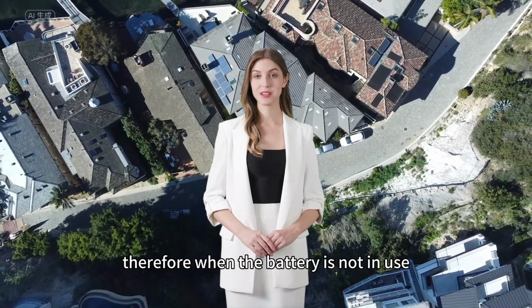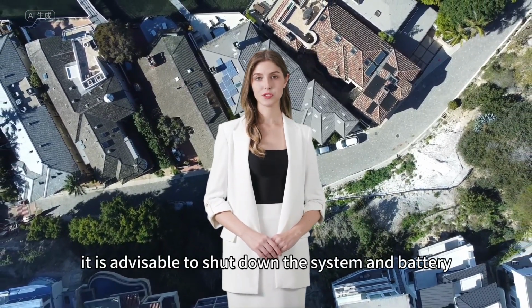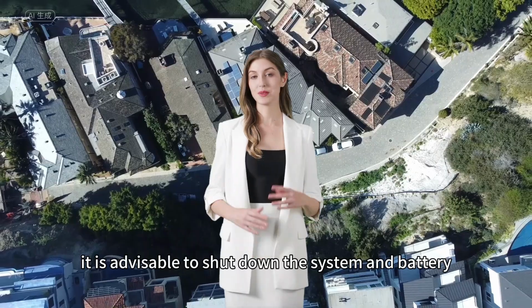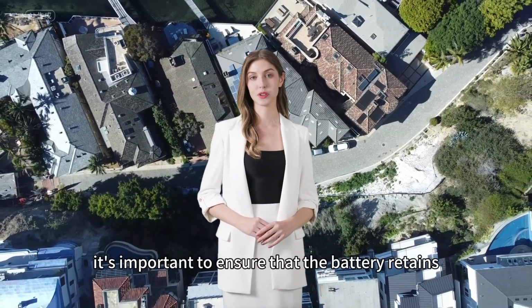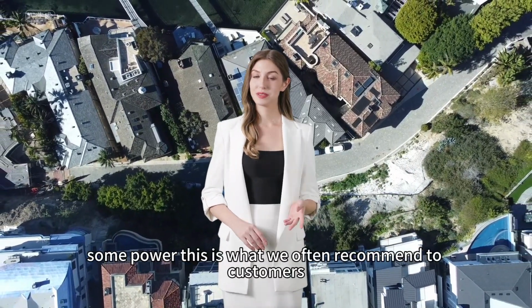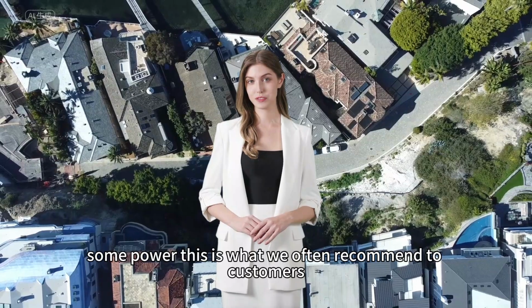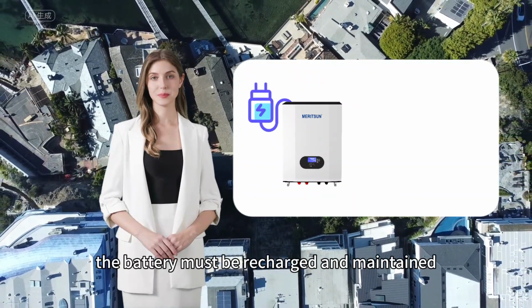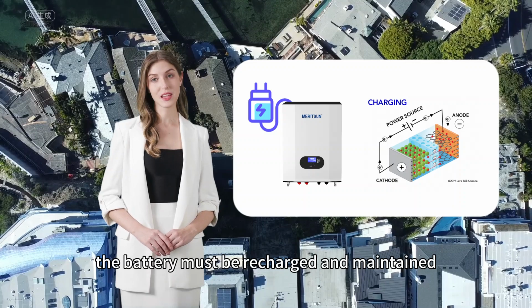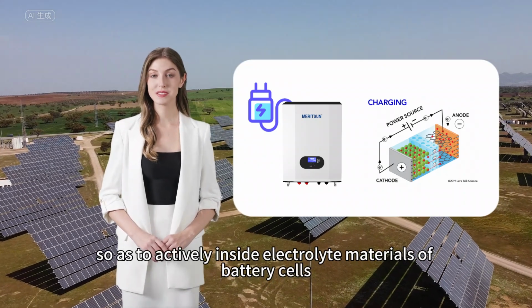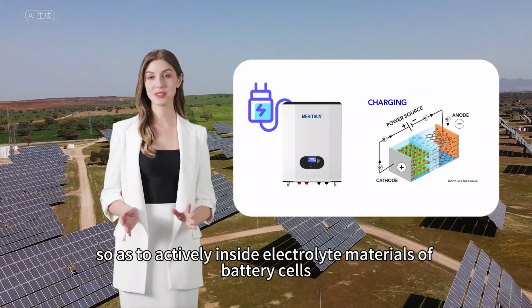Therefore, when the battery is not in use, it is advisable to shut down the system and battery. Furthermore, it's important to ensure that the battery retains some power. This is what we often recommend to customers. After a certain period of time, the battery must be recharged and maintained so as to keep the electrolyte materials of the battery cells active.